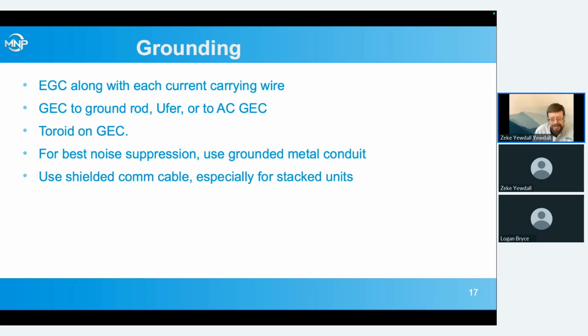Best practice, like I said, when doing comm cable, is if we're running Ethernet long distance, is to run fiber with converters on the end. They're under $100 for the converters, and it really prevents that being a source of lightning strikes coming in. For shorter comm cables, using shielded cable, especially if you're running it in the same gutter with all your AC power wires. And for stacked units, the inverters are pretty sensitive to the quality of that stacking cable that goes between the units.